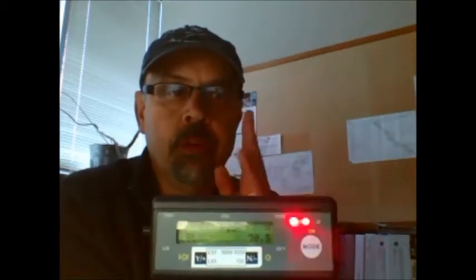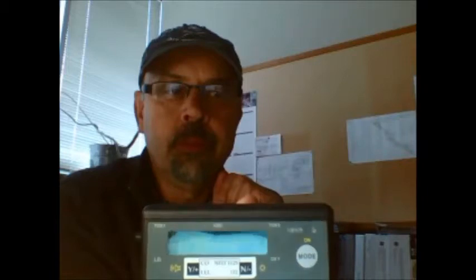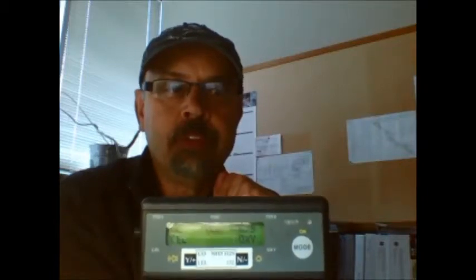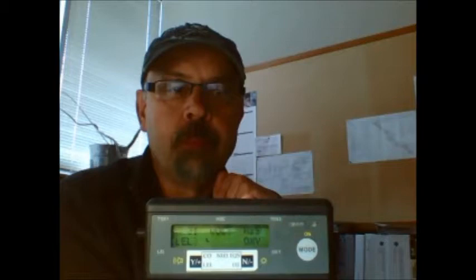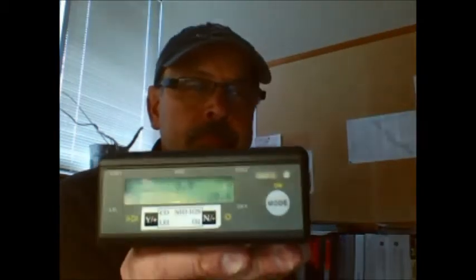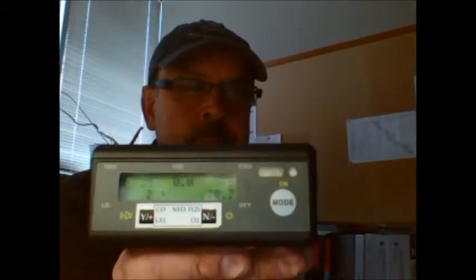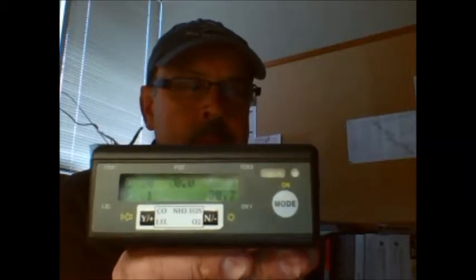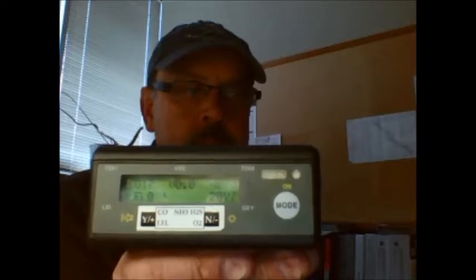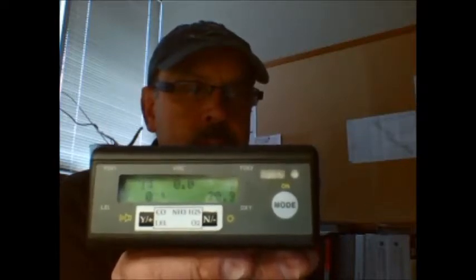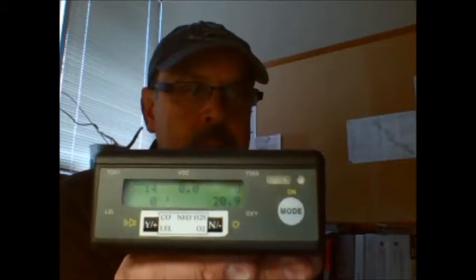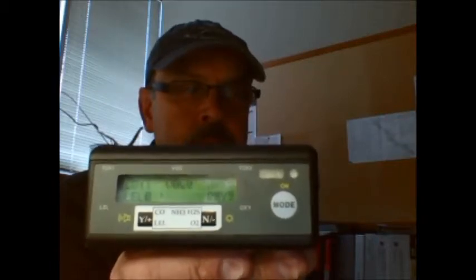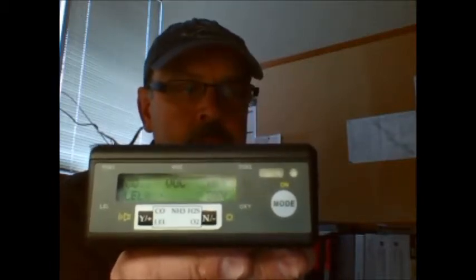And now you hear as the cells go back to 0, the alarms will drop out. And it takes them a little bit. The CO will take a little bit. It's coming down, as you can see. The oxygen is back, the LEL is back, and the CO is coming down ever so slowly. I won't keep doing that. It's coming down on that 9.